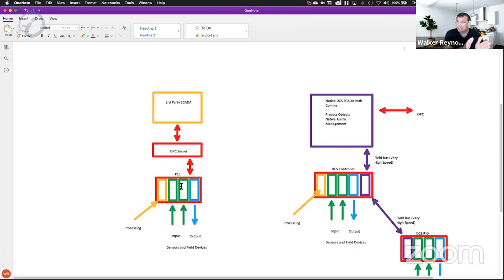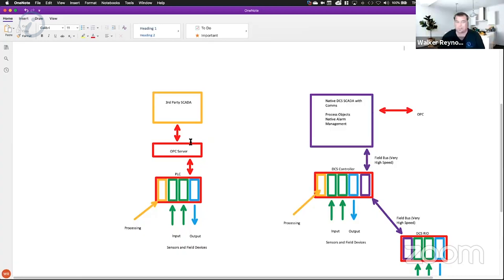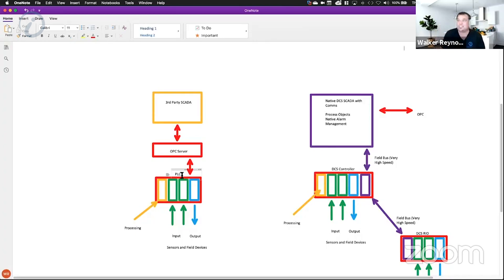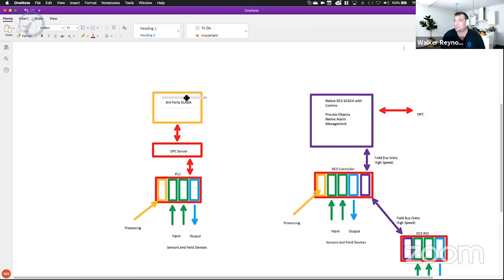The PLC generally talks to the outside world not directly — it talks to an OPC server. This would be something like Kepware, or DASABCIP from AVEVA, or Matrikon OPC. There are lots of pieces of software that talk to this PLC through an Allen Bradley communications driver. All the software that wants to get data from the edge from the PLC is going to get it through that OPC server. You also add in some third-party SCADA software — Wonderware, iFix, Ignition, Factory Studio — all of those talk to the OPC server.